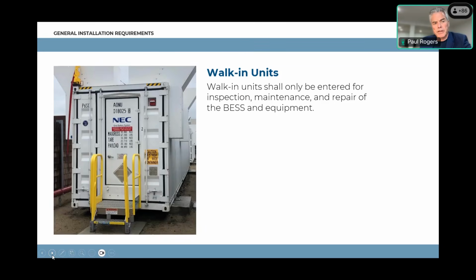Walk-in containers—there's a definition for these in the code. A walk-in container or walk-in unit is treated as if it were a building, meaning someone can physically walk inside to do repairs, replacements, and maintenance of the battery energy storage systems. They're required to have a sprinkler system on the inside because it's treated as an indoor installation. This should not be equated with cabinets, where no one can walk in—there's a separate definition, and it's important everyone understands the difference. If you cannot walk into the system, it's considered a cabinet and does not require the sprinkler system.